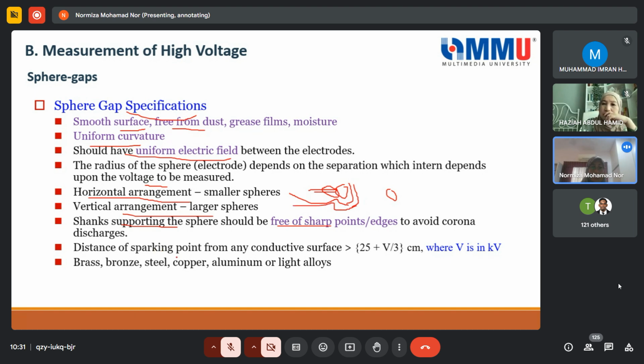So for the distance of the sparking point from any conductive object, we use a formula: it should be more than 25 plus V over 3, where V is in kV and is the voltage to be applied. For example, if you use 100 kV, you inject 100 kV. So 100 divided by 3 is 33, plus 25. So it becomes how much? 58, right? Yeah, so the distance should be 58 cm.